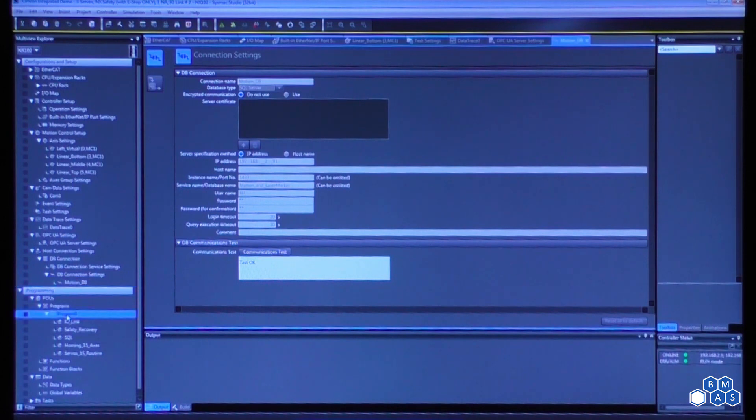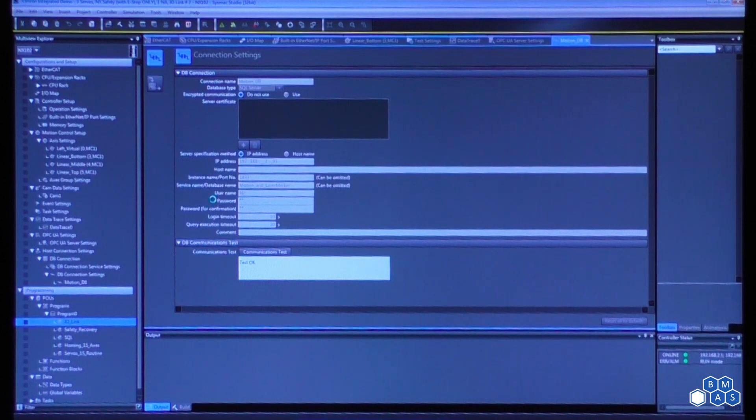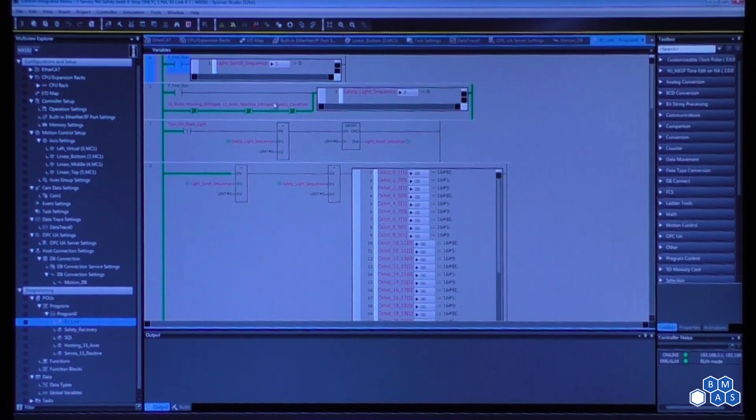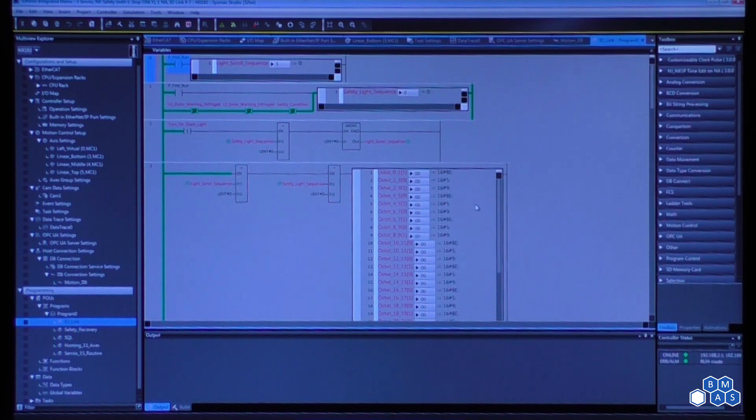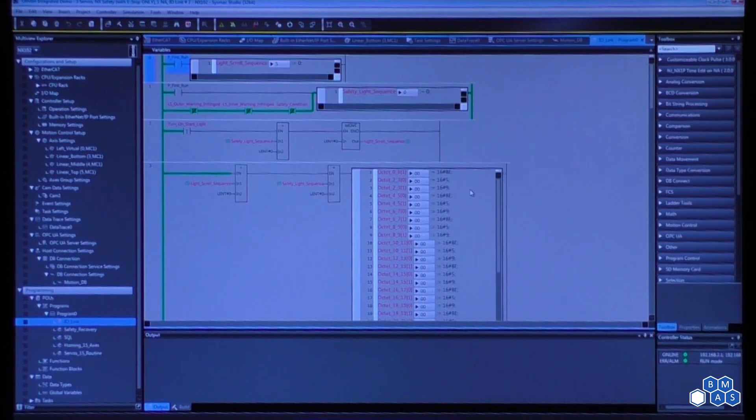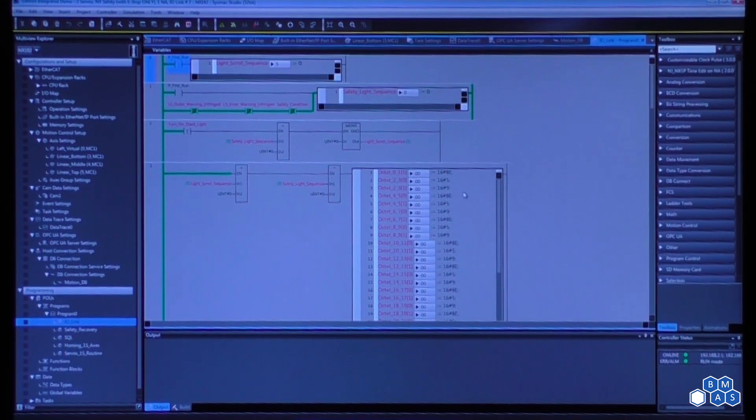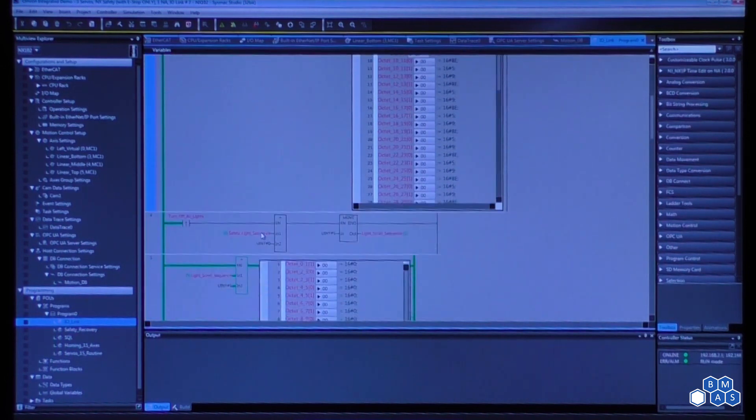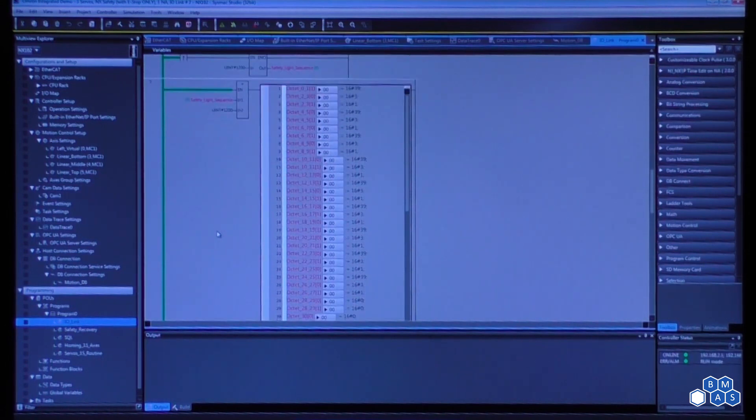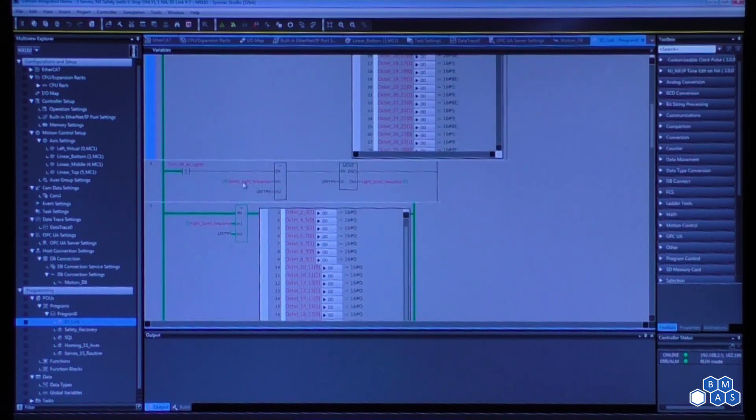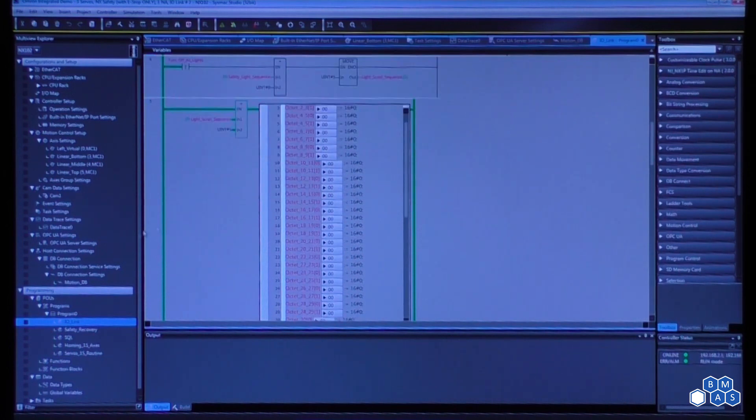So the program zero, you'll notice down at the bottom, now that we've configured all of our initial device configuration setup, we'll go in and start working on our code. Now one of the things I want to point out within the code is that Omron has an ability to do what's called inline structured text. So you'll see your standard ladder logic, but then you can also do what's called inline structured text. This is, for all intents and purposes, a very advanced structured text language where you can get up to a thousand lines of code within one of these windows. This is very powerful for doing things like for-next loops for populating data over an array of elements or just to make things faster. So this shows examples of how you can use combinations of ladder logic and structured text. Quite honestly, both of them have benefits, and having that combination and taking advantage of each of their strengths is really something that is very beneficial.